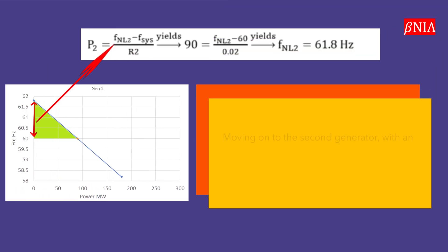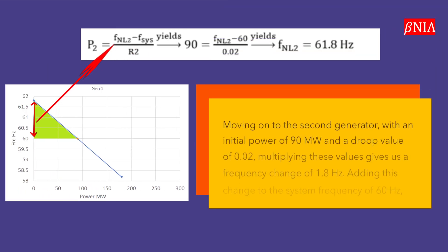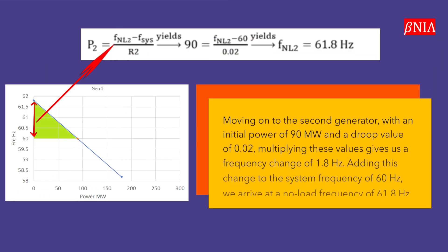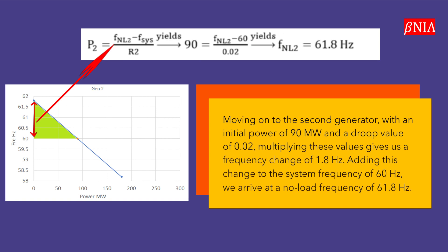Moving on to the second generator, with an initial power of 90 MW and a droop value of 0.02, multiplying these values gives us a frequency change of 1.8 Hz. Adding this change to the system frequency of 60 Hz, we arrive at a no-load frequency of 61.8 Hz.